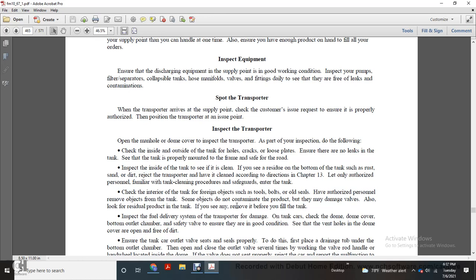Inspect the inside of the tank for cleanliness and residue at the bottom of the tank, such as rust, sand, dust, sediment, and debris. Have it cleaned according to the directions in Chapter 13. Let only authorized personnel familiar with tank cleaning proceed with the safeguards and cleaning of the tank.